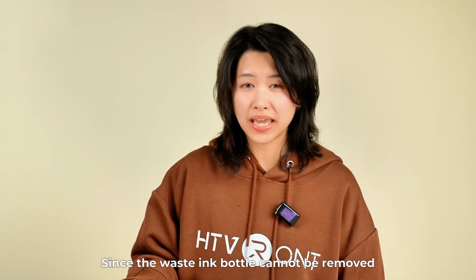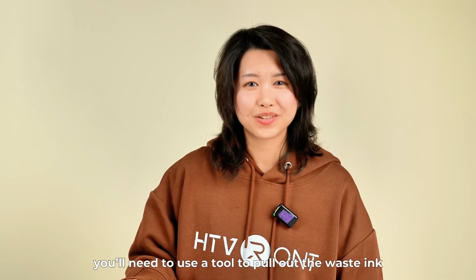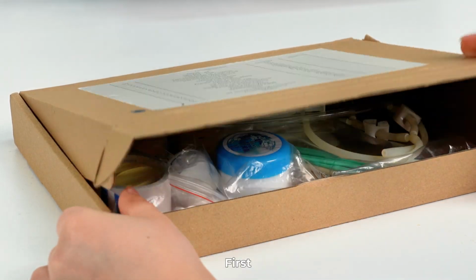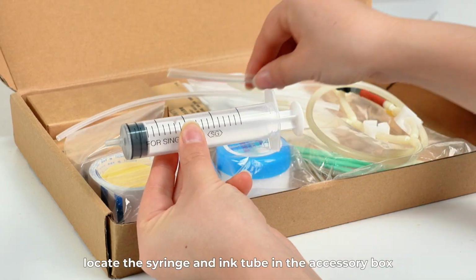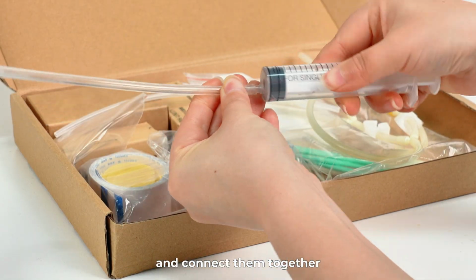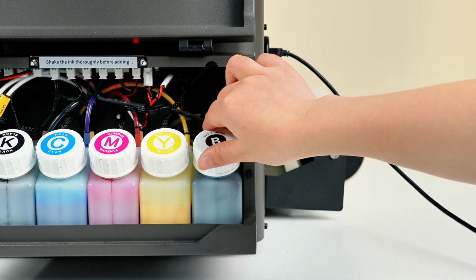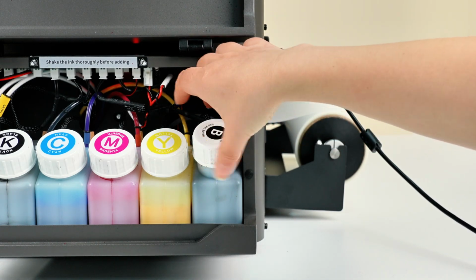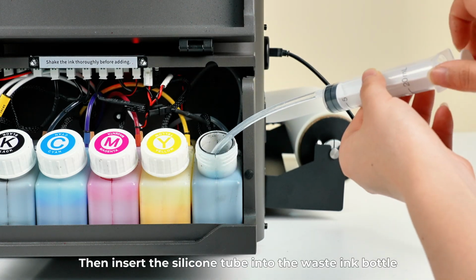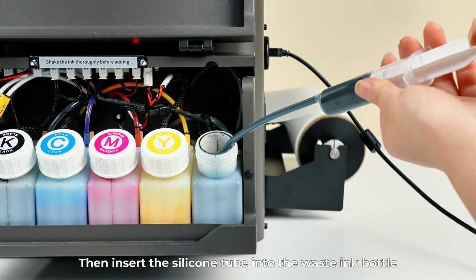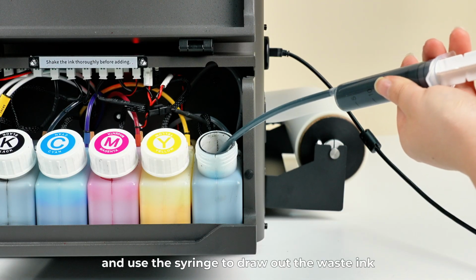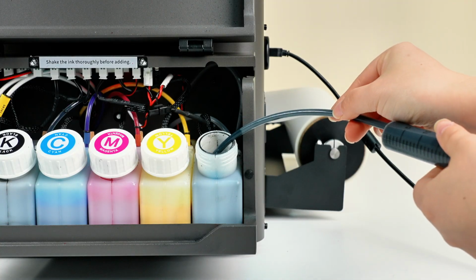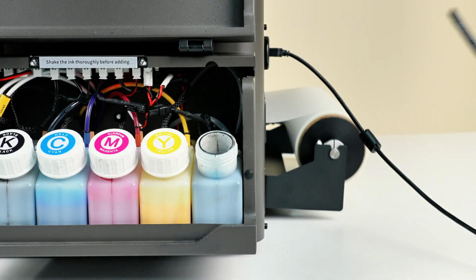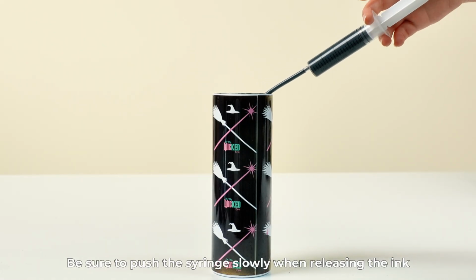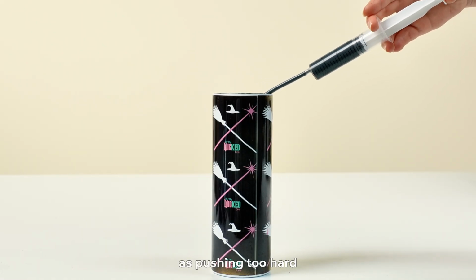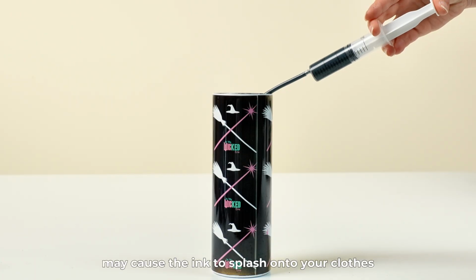Since the waste ink bottle cannot be removed, you will need to use a tool to pull out the waste ink. First, locate a syringe and ink tube in the accessory box and connect them together. Then, insert the silicone tube into the waste ink bottle and use the syringe to draw out the waste ink. Be sure to push the syringe slowly when releasing the ink, as pushing too hard may cause the ink to splash onto your clothes.